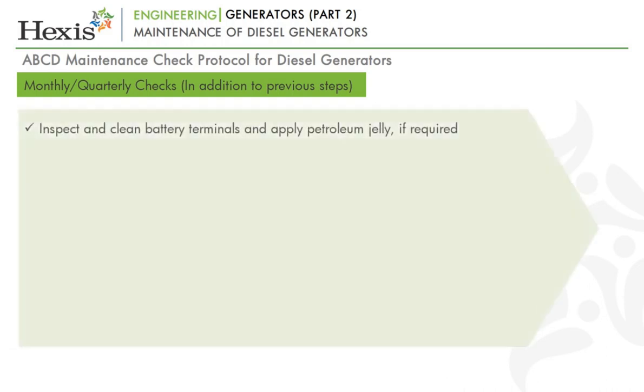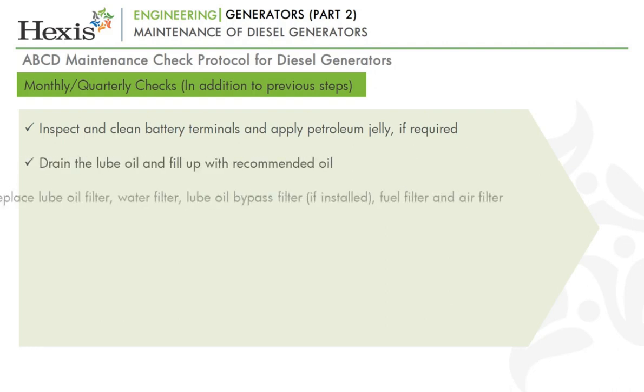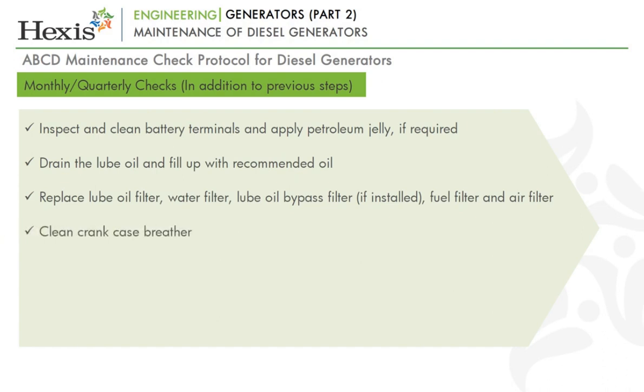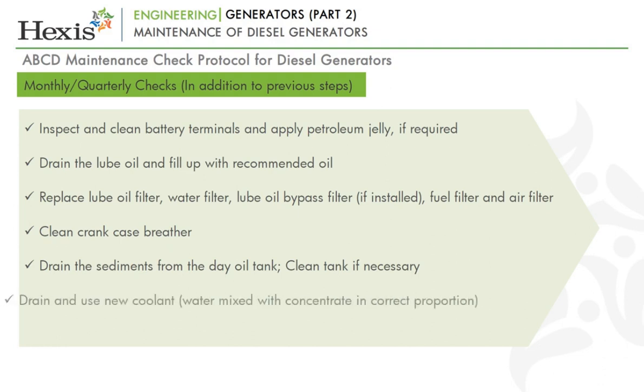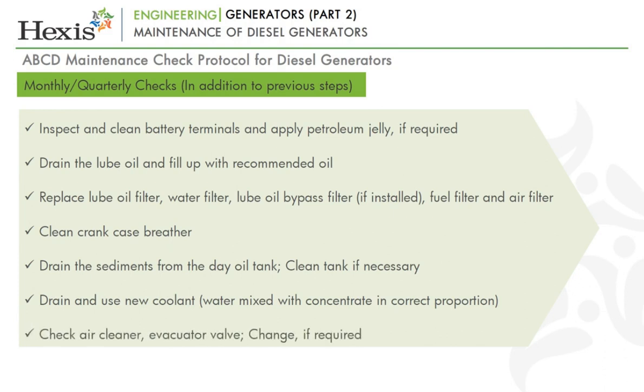Inspect and clean battery terminals. Apply petroleum jelly if required. Drain the lube oil and fill up with recommended oil. Replace the lube oil filter, water filter, lube oil bypass filter if installed, fuel filter and air filter. Clean the crankcase breather. Drain the sediments from the day oil tank, clean tank if necessary. Drain and use new coolant. A coolant is water mixed with concentrate in correct proportion. Check the air cleaner and evacuator valve. Change these if required.